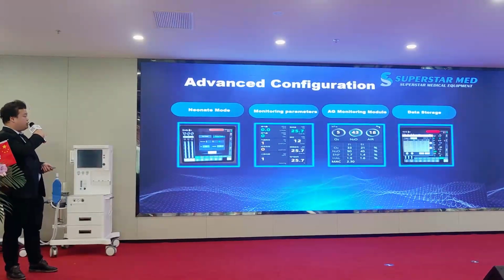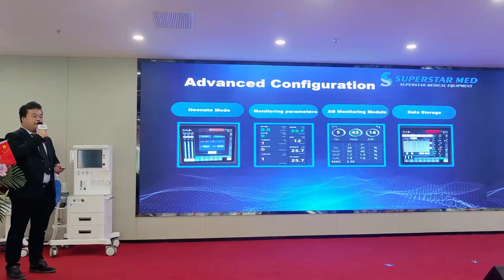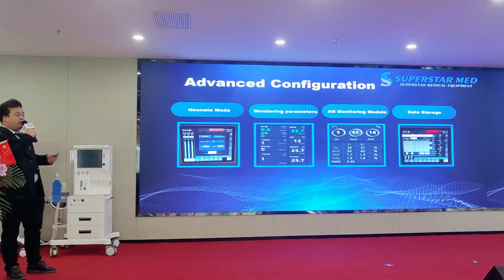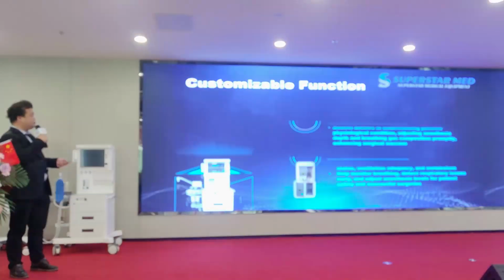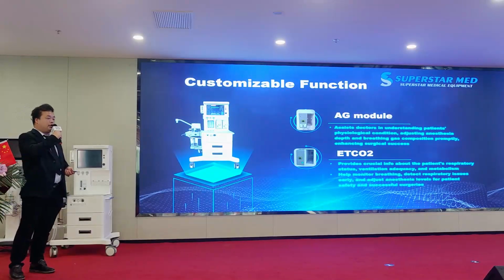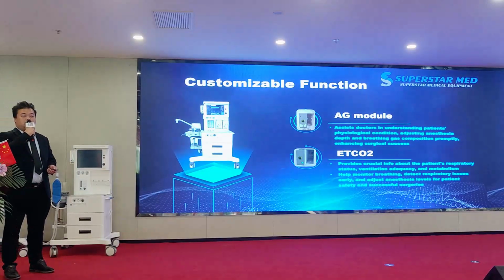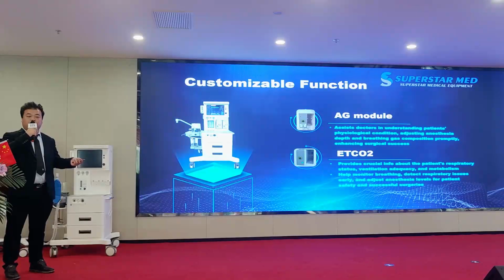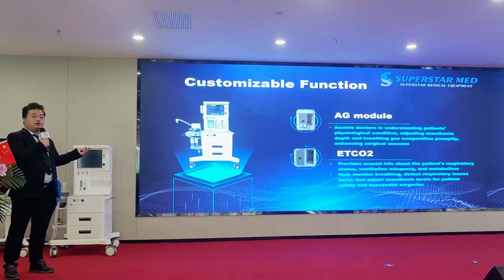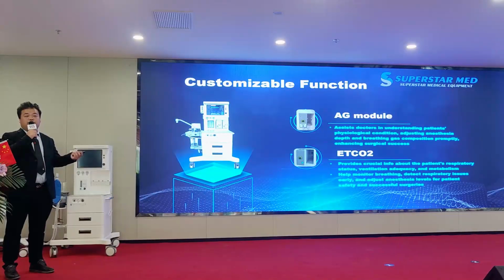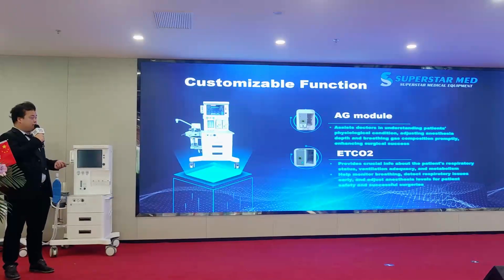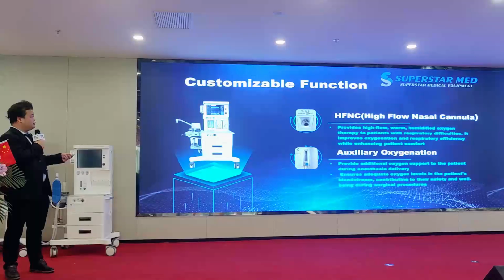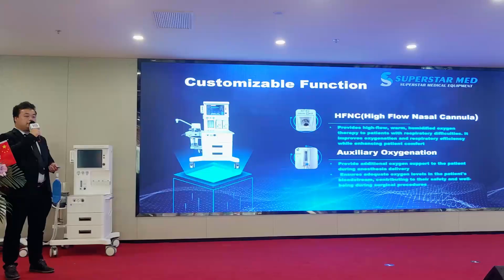And these are some monitoring parameters. You need to load the AG monitoring module and data storage. So for this machine, we're also making the AG module on our anesthesia machine directly, not only using the patient monitor, but already shown on our anesthesia machine. It's on the left side of the machine. And the AG module and the ETCO2, we are using a modular design. That means even if the hospital doesn't have the requirement at first, later, if they want to add the function, they just buy the module and plug it in. Then it's very easy for them to use. And even for this kind of module, you can plug it in to use on another anesthesia machine. It's also very easy and fast. And also the HFNC and the auxiliary oxygen inlet.